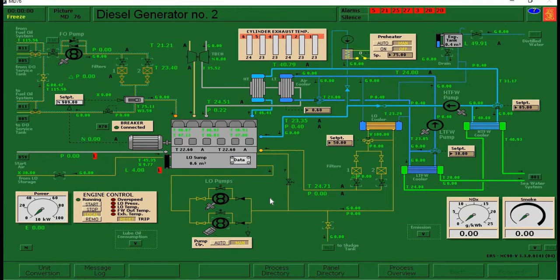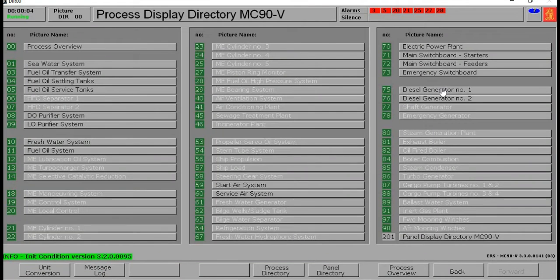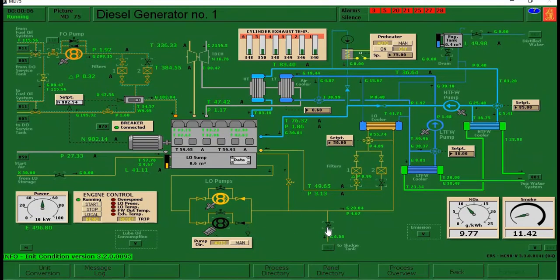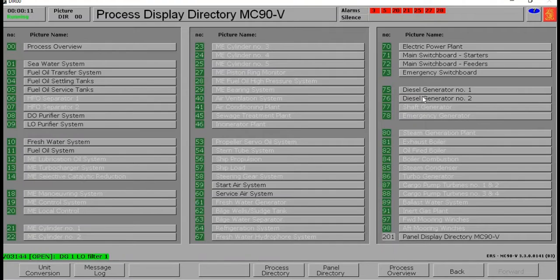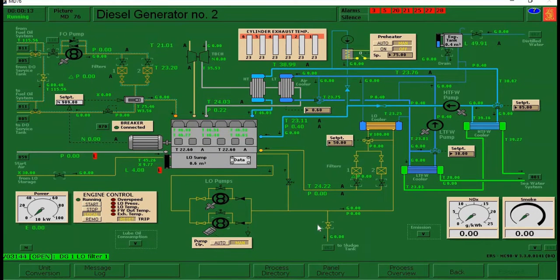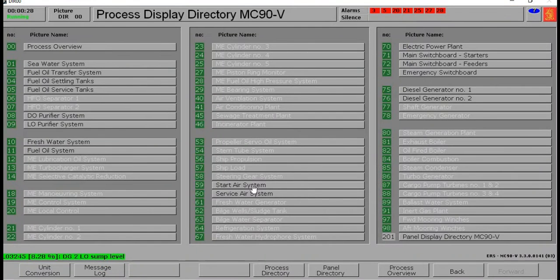So, before we start, we need to press F1. You will have 10 minutes to fulfill the assessment. So, let's go to diesel generator 1. Check our system here. Discharge valve closed, filter open. Okay. Let's go to DG2. So, we need to turn this closed and this valve open, and our makeup valve open to fill our sump here. Let's go to the starting air system.